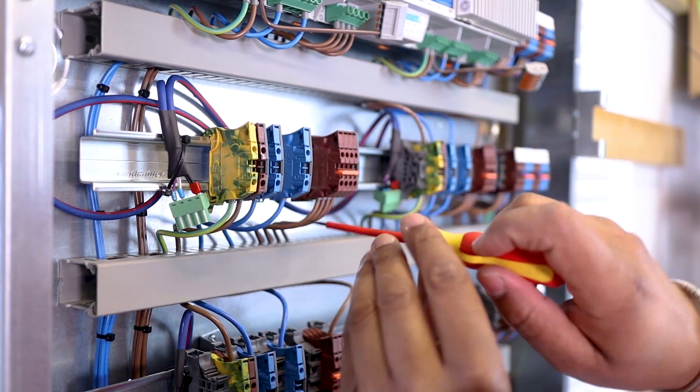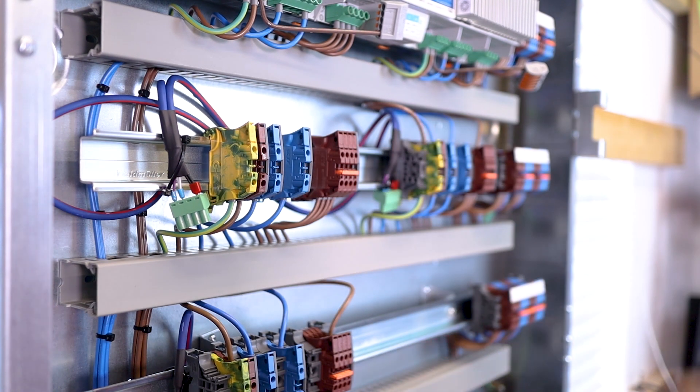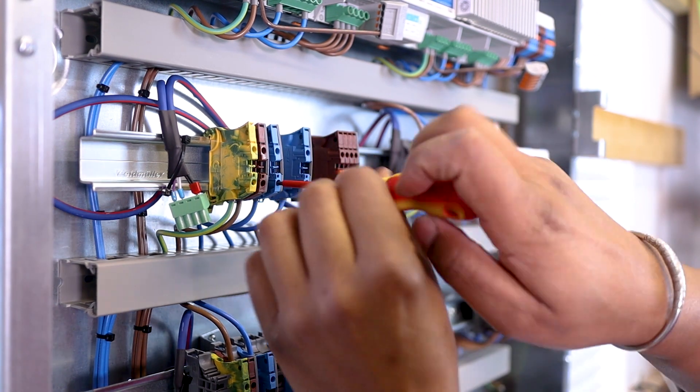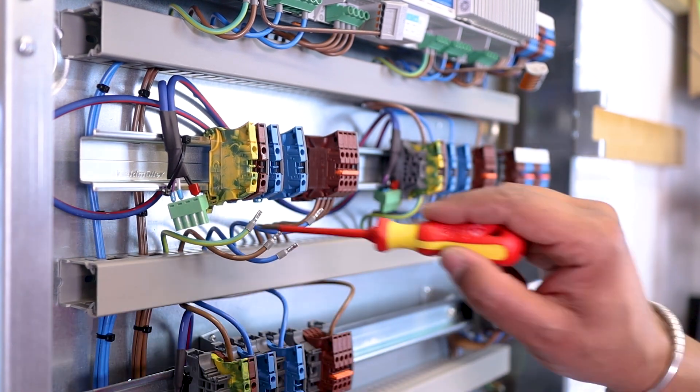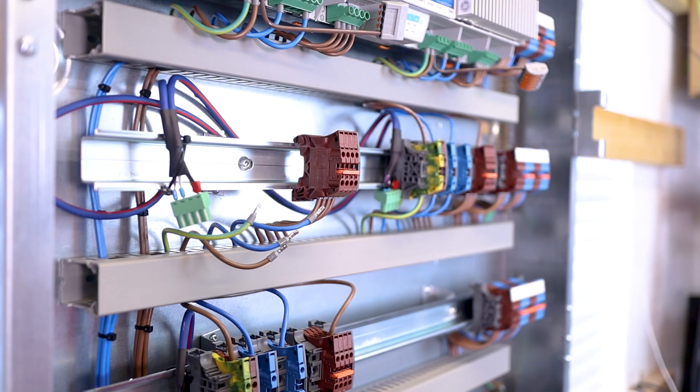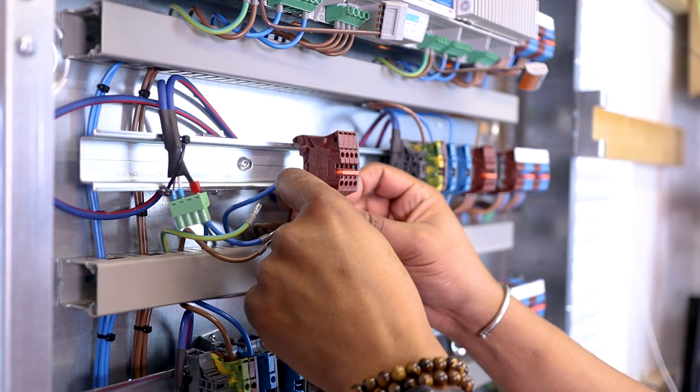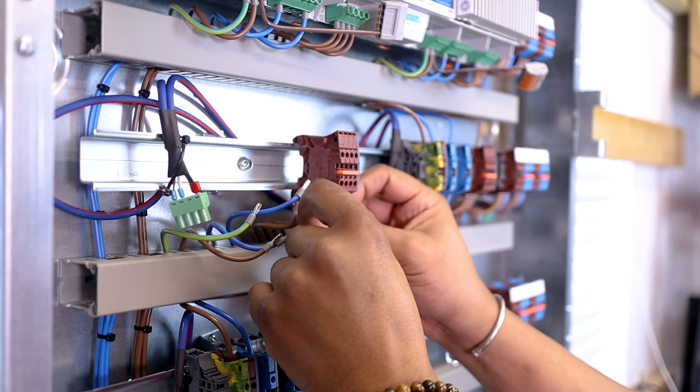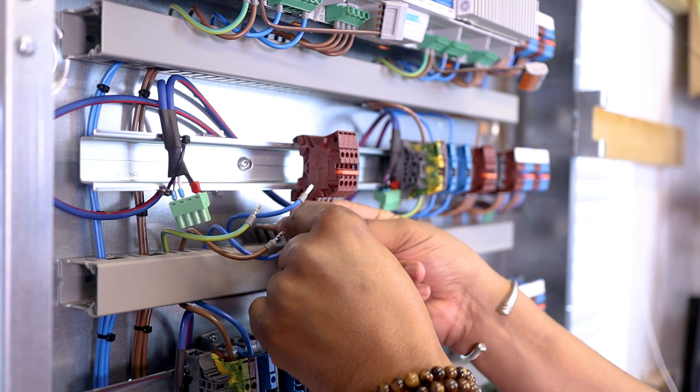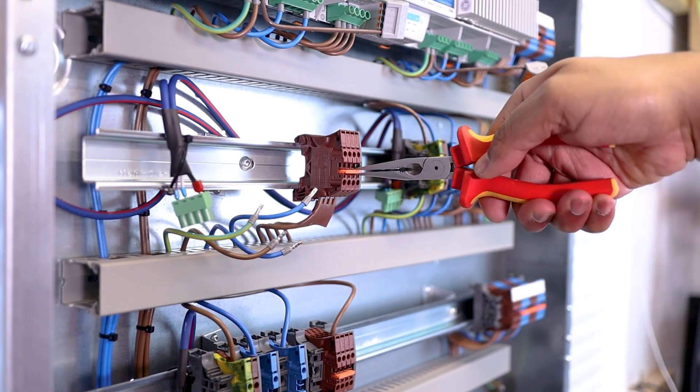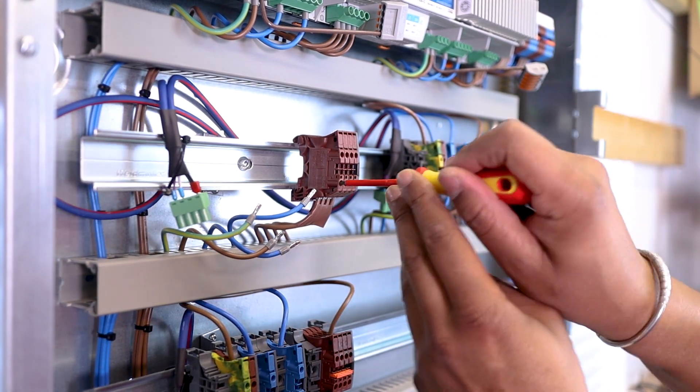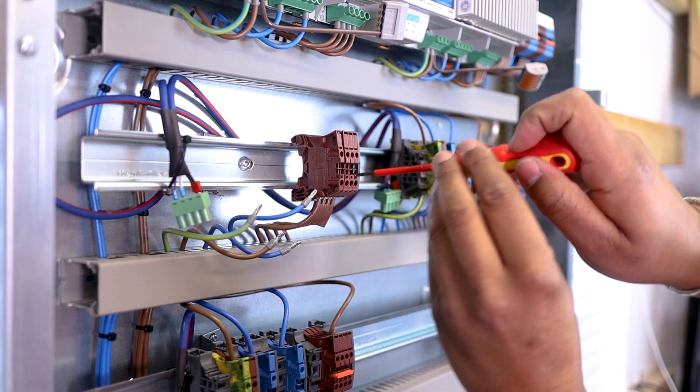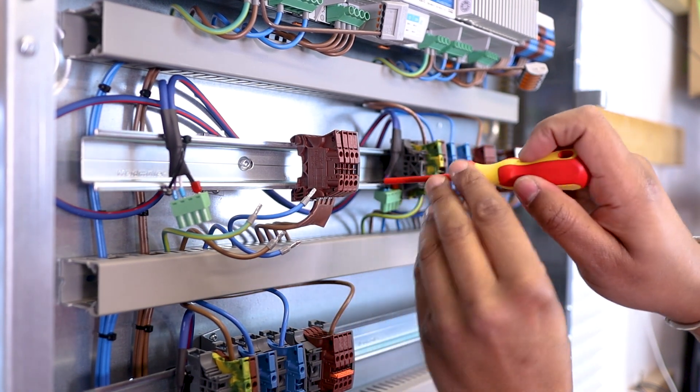There we go! Now, let's release those cables first from their respective connectors, so I can remove them to install my Lutron module instead. Here, I use a bit of tape to keep the order of the four module output cables, as they match the order to which they wire back to the connectors, where the lighting circuit will be landing on the right-hand side of the panel.